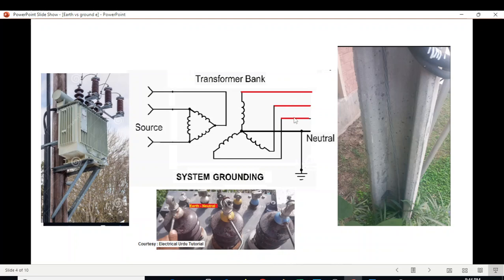These three are the live wires or the phase wires, and this is the neutral point. So you can see here the three smaller ones for 220, and this white one is for the neutral wire or the ground wire. Now at the transformer terminal, you can see this wire going down and going underneath. It has been dug underneath. So the neutral point is also connected to the ground. So remember that the neutral is grounded at the transformer terminal. And this whole system is called system grounding.